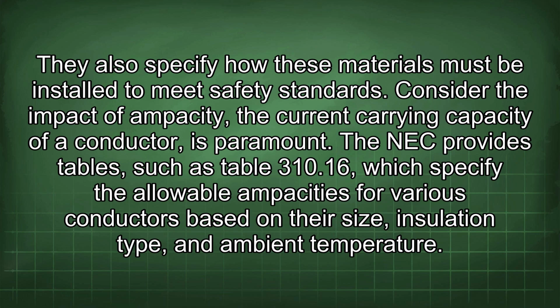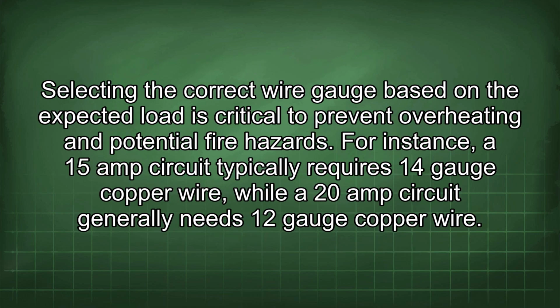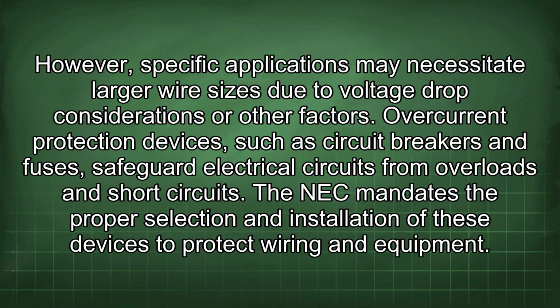Consider the impact of ampacity. The current carrying capacity of a conductor is paramount. The NEC provides tables, such as Table 310.16, which specify the allowable ampacities for various conductors based on their size, insulation type, and ambient temperature. Selecting the correct wire gauge based on the expected load is critical to prevent overheating and potential fire hazards. For instance, a 15-amp circuit typically requires 14-gauge copper wire, while a 20-amp circuit generally needs 12-gauge copper wire. However, specific applications may necessitate larger wire sizes due to voltage drop considerations or other factors.